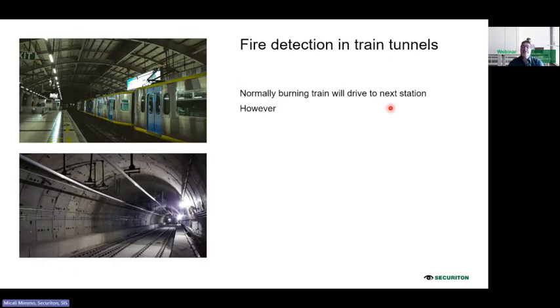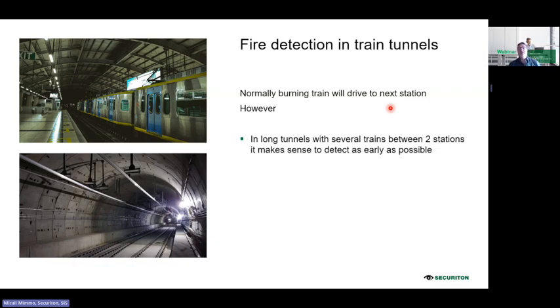Then fire detection in train tunnels will happen normally if the train is burning. That means they have to drive to the next station. However, if you have tunnels, especially metro tunnels, you may have different train sections between 2 or 3 stations, and therefore it's important to have this kind of fire detection system, because you can control if there is a fire. And if there is a fire, you also have to give the signal to stop all the trains, because maybe one train which is on fire cannot go to the next station because the next station is already occupied by another train. So all this information is important for the operator to control the traffic in case of a fire.